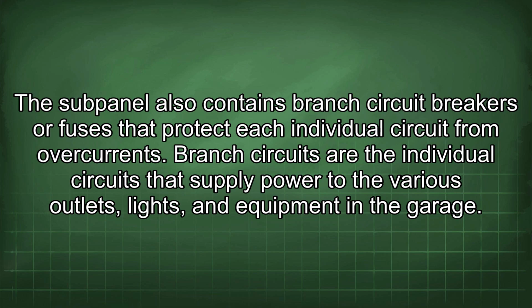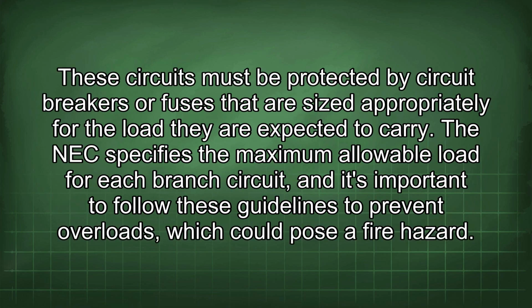Branch circuits are the individual circuits that supply power to the various outlets, lights, and equipment in the garage. These circuits must be protected by circuit breakers or fuses that are sized appropriately for the load they are expected to carry. The NEC specifies the maximum allowable load for each branch circuit, and it's important to follow these guidelines to prevent overloads, which could pose a fire hazard.